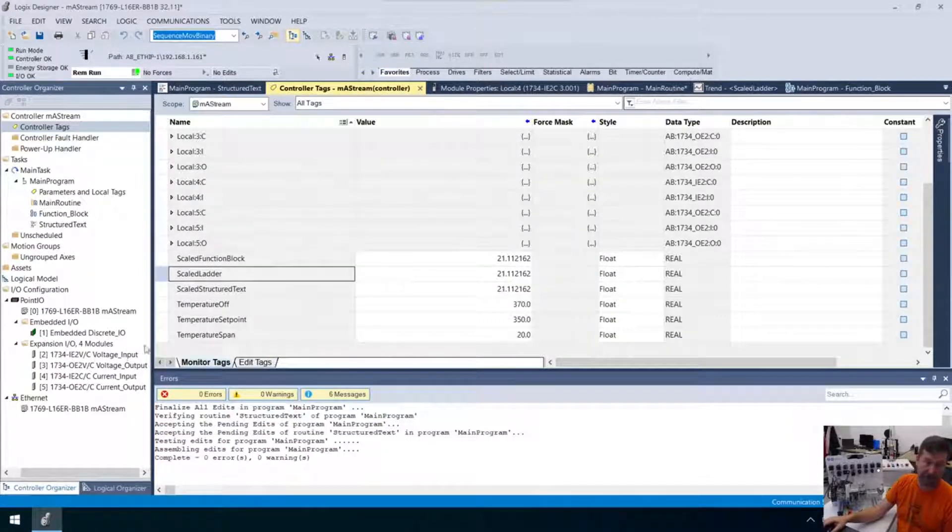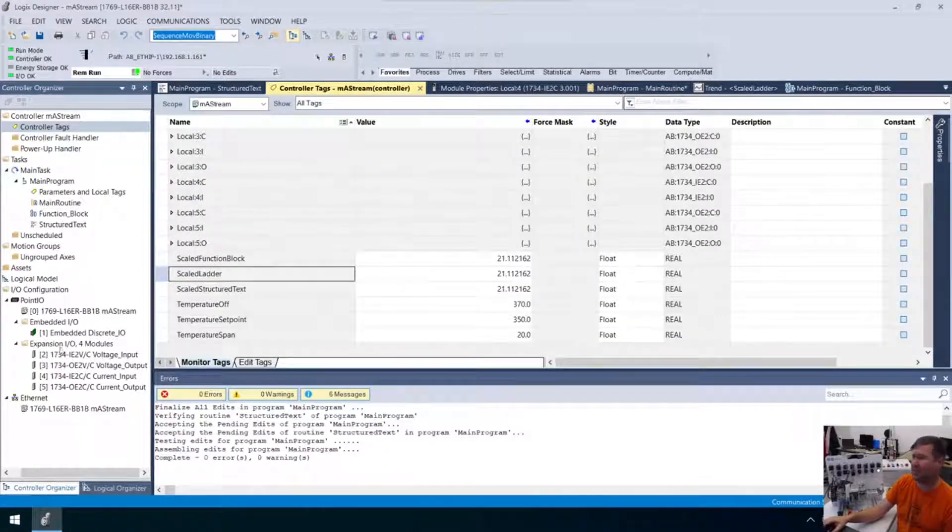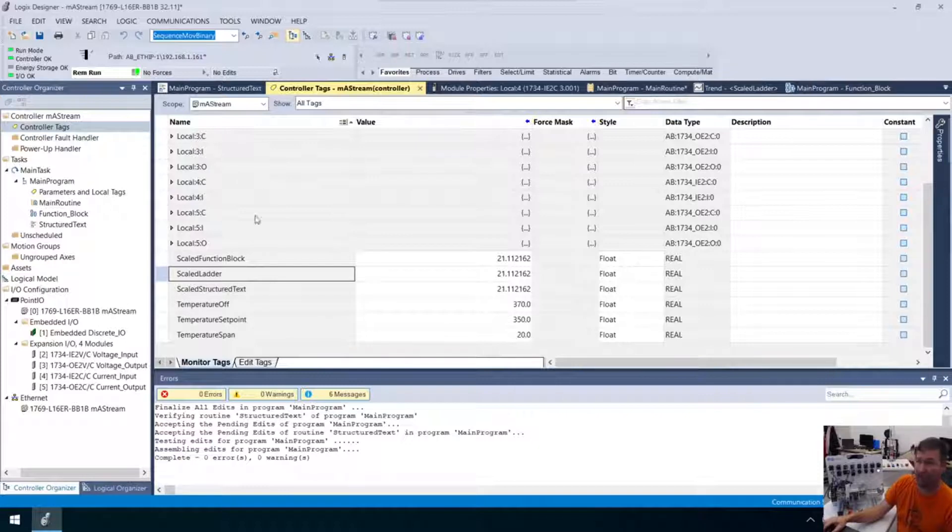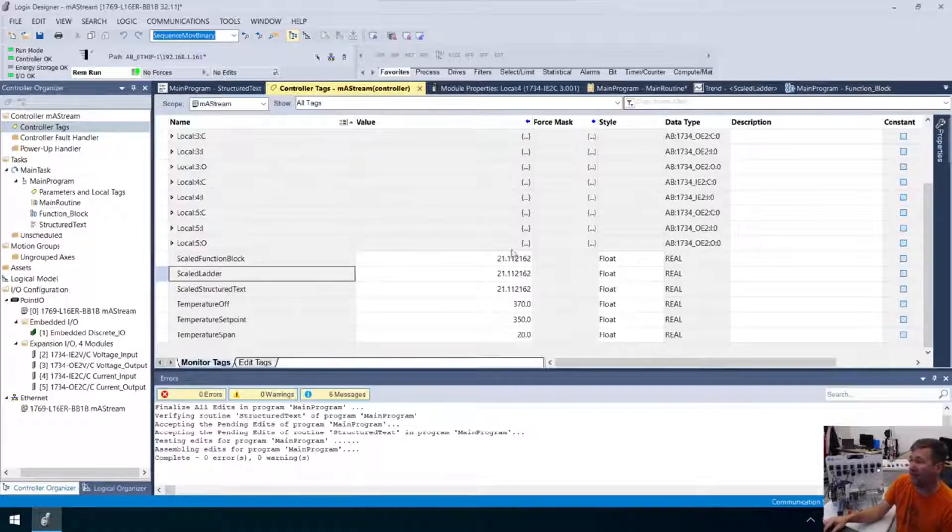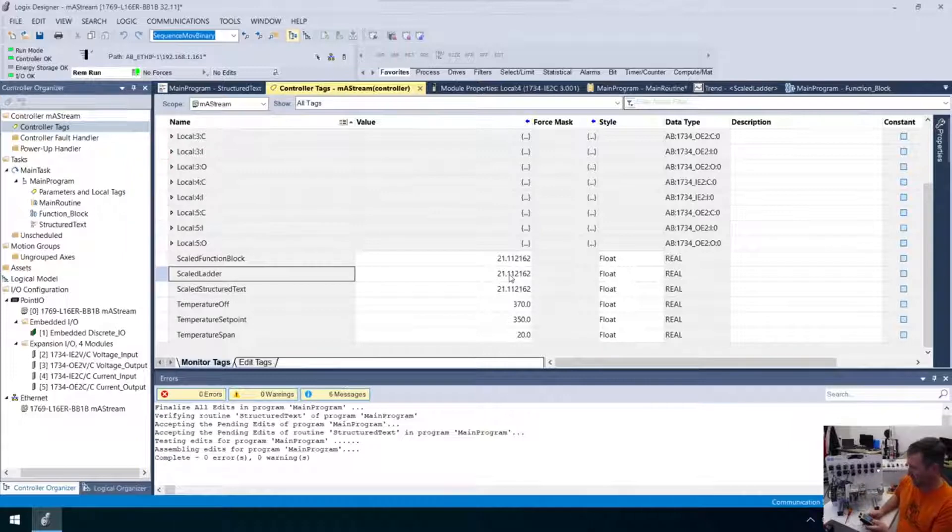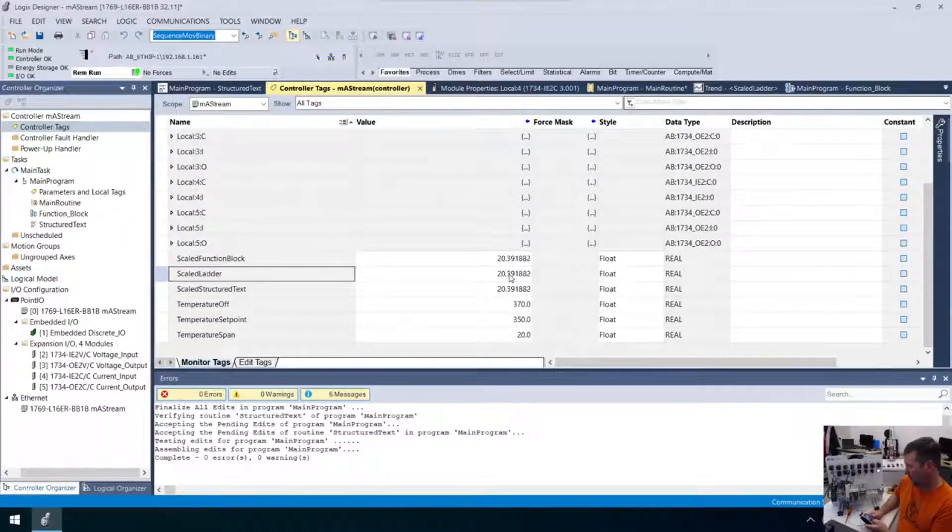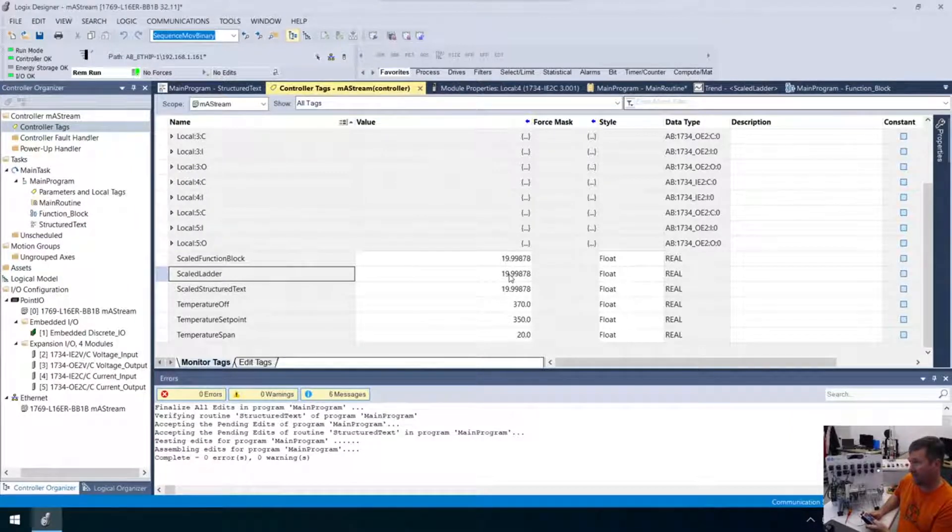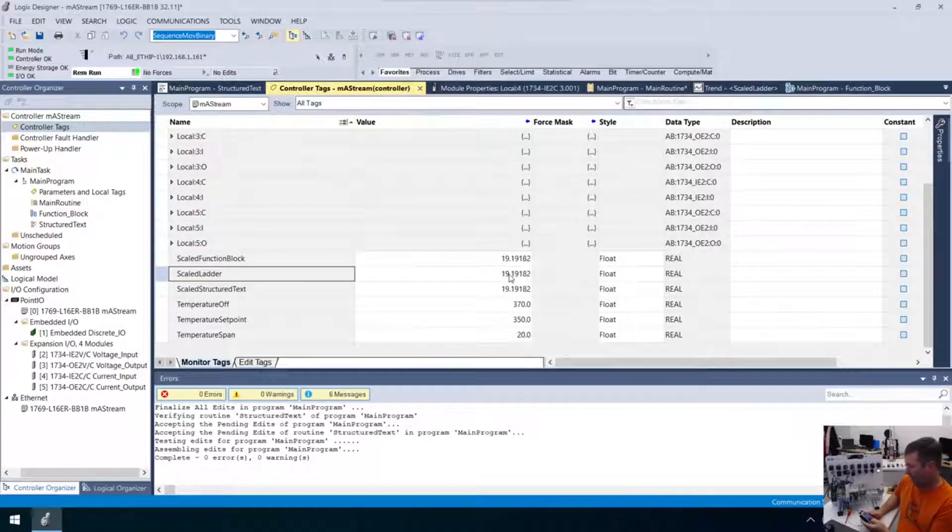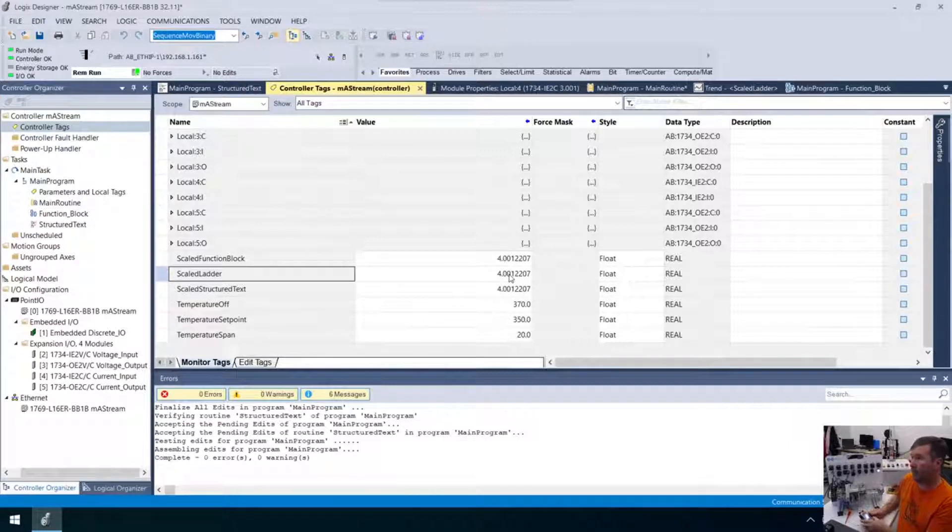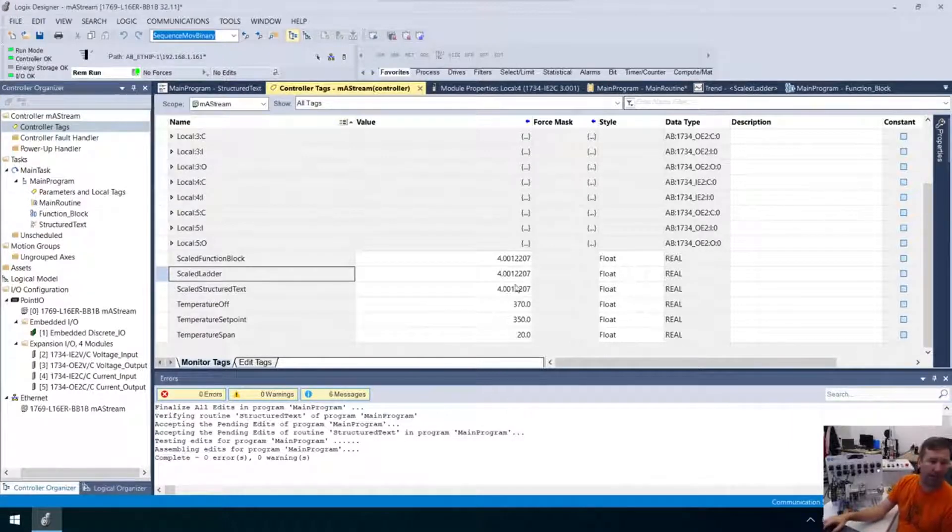Make sure you know that there's no verify on that. That's probably something we should do in a video. Because, yeah, with that delete button I just did, that thing is gone. No more. There's no undo on it, either. Okay, but now, look, all these values are identical. And so, yeah, we'll drop it to 20 milliamps. And, yeah, we're still 19.9998, which is pretty close. And we're going to drop down to 4 milliamps. And at 4 milliamps, there you go. They're all identical, right, at 4.01.